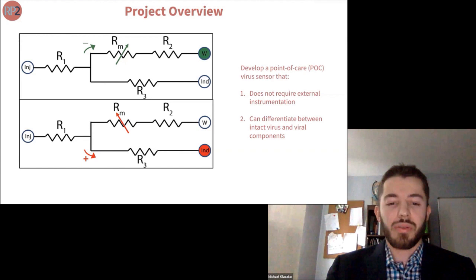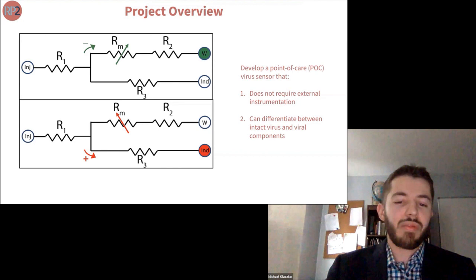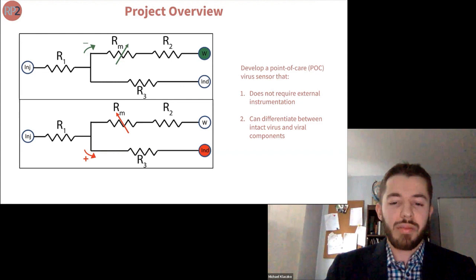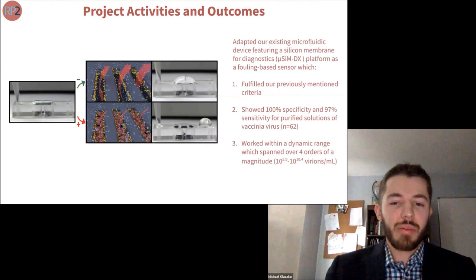In a positive test result, virus capture clogs the membrane and increases its resistance so that the bottom path becomes the new path of least resistance. In this manner, we are able to determine if a test is negative or positive depending on where fluid protrudes from the device.